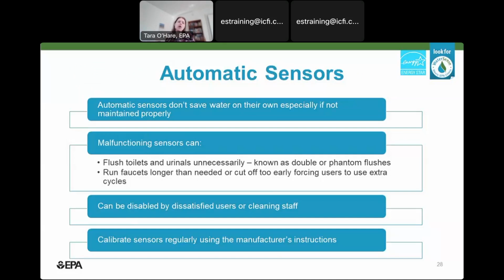As I mentioned a minute ago, one thing to keep in mind is that automatic sensors on fixtures don't save water on their own, especially if they're not being maintained properly. So malfunctioning sensors can obviously have faucets that run longer or cut off too early, forcing users to use an extra cycle of water use, or the toilets and urinals can be flushing unnecessarily. So you really want to calibrate them regularly using the instructions from the manufacturer, and that will help to make sure that it's actually performing as expected.